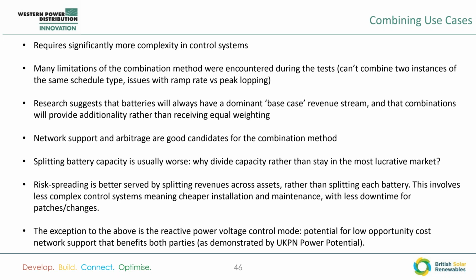Splitting capacity to do 2 things at once, in a way to sort of spread bets, hurts returns in a fiercely competitive business. So you pick the most lucrative use case and you do that. You don't try and do 3 at once with different parts of your battery capacity. There's slight variations on that. If you're doing the local support and you only have to offer a third of your battery to do that, then you leave the rest of your battery doing your base case. That's better, because you're getting more revenue from that third and then still getting your standard revenue from the other 2. But in terms of a sort of bet spreading type scenario, it's not right.